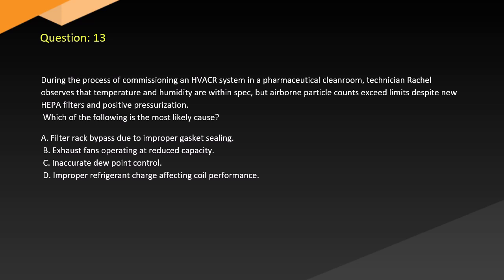Question 13. During the process of commissioning an HVACR system in a pharmaceutical cleanroom, technician Rachel observes that temperature and humidity are within spec, but airborne particle counts exceed limits despite new HEPA filters and positive pressurization. Which of the following is the most likely cause? A. Filter rack bypass due to improper gasket sealing. B. Exhaust fans operating at reduced capacity. C. Inaccurate dew-point control. D. Improper refrigerant charge affecting coil performance.